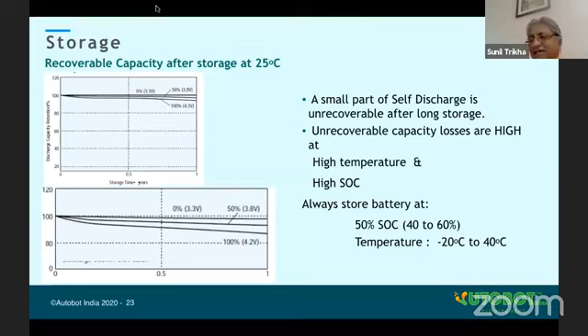Even kept in factory, batteries unused, it is always brought to a 50% state of charge and kept. This is important. One must understand why batteries after use or after testing. Even if you test a battery, after testing you will be getting between 40 to 60% state of charge. After testing the capacity, you are required to recharge to 50% and then keep it. Secondly, you must store between -20 to 40 degrees centigrade. Don't store at high temperature because you will be losing some capacity permanently.